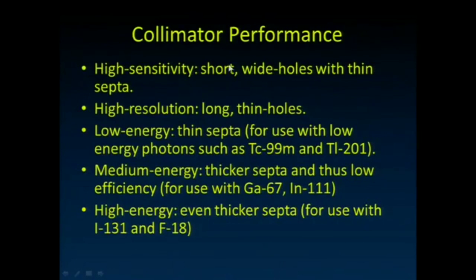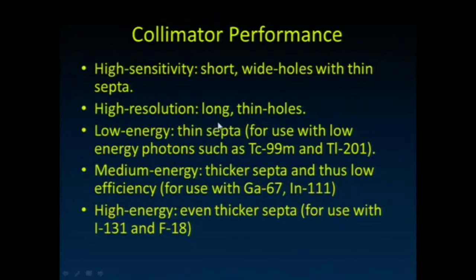High sensitivity collimators allow collection of as much radiation as possible; they tend to have short, wide holes with relatively thin septa. High resolution collimators have long, thin holes. Low energy collimators image radionuclides with relatively low energy gamma rays and don't need thick lead septa. High energy collimators, of course, have very thick septa to stop high energy gamma rays from penetrating through.